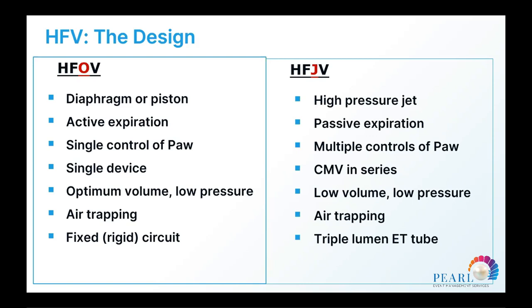The problem with the jet ventilator is that you have to have two ventilators, because the concept of the jet is that you give inspiratory pressure, but you depend on the lung recoil for the expiratory phase. So there's no active expiratory phase. That's different from the machine that we use right now, which is the high frequency oscillator, which has an active inspiration and an active exhalation phase.